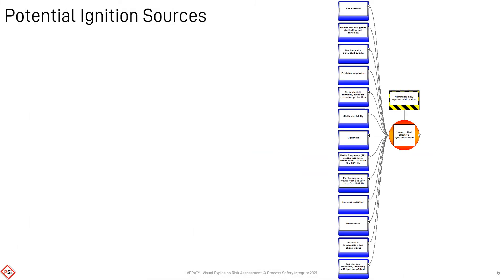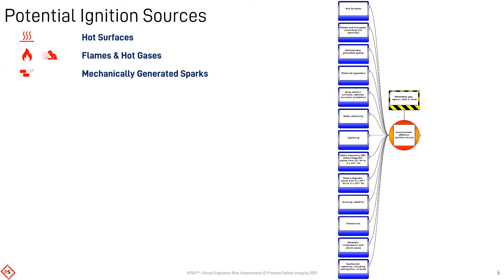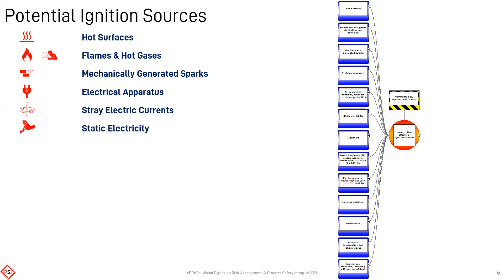A list of potential ignition sources has been developed from EN 1127 Part 1. These threats are: hot surfaces; naked flames or hot gases, for example from welding; mechanically generated sparks, typically friction; electrical apparatus, which may create sparks; stray electric currents; and static discharges.